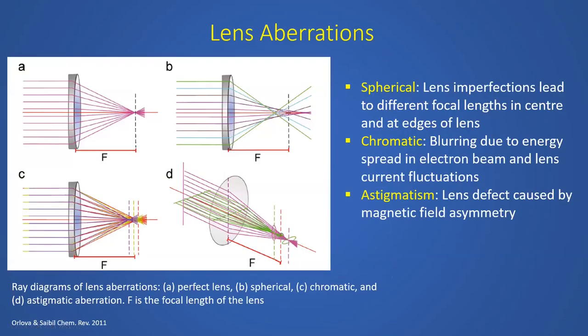So these are the lens aberrations that you typically have with any microscope: spherical aberration, chromatic aberration, and astigmatism. Spherical aberration basically results from lens imperfections, so you have different focal lengths at the center and the edges of the lens. This is where the apertures come into place. You can cut off the peripheral electrons by using proper apertures. Chromatic aberration is basically blurring due to different energy spreads in the electron beam and current fluctuations. And astigmatism is a lens defect caused by magnetic lens asymmetry. This is corrected by stigmators.